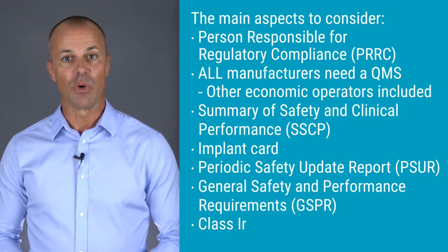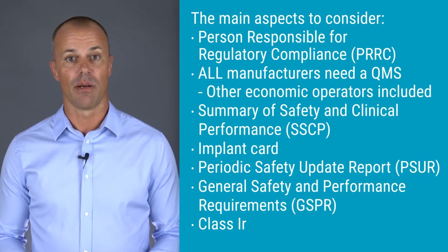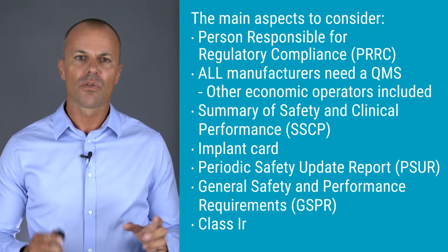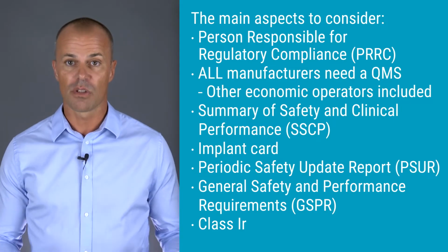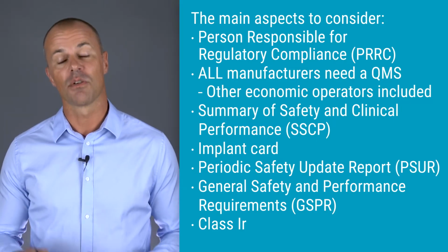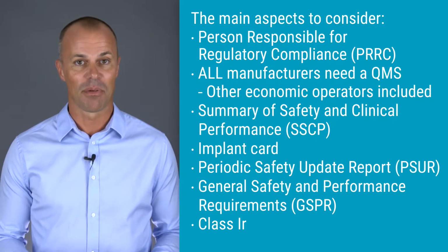Not to be mixed up with reprocessing, which is another thing under MDR. This new class also requires the manufacturer to involve a notified body in the conformity assessment to get market access in Europe. Those were the major things I wanted to highlight. As I mentioned in the introduction, I will not only try to give an overview of the MDR from the manufacturer's perspective, but also a tiny bit from a notified body's perspective. So let's continue with the definition of those two and some more.